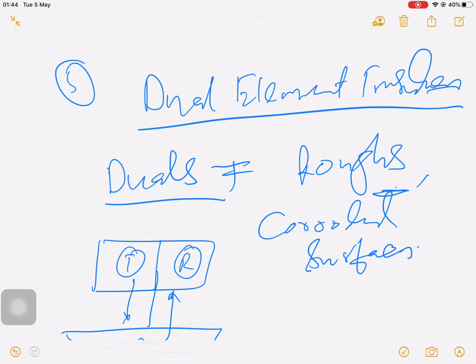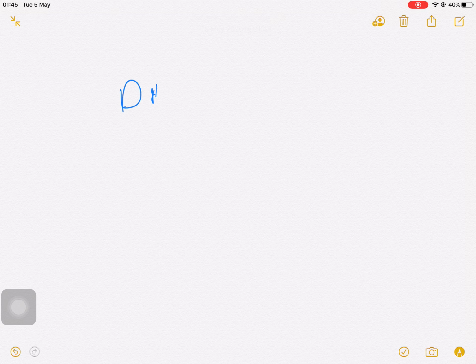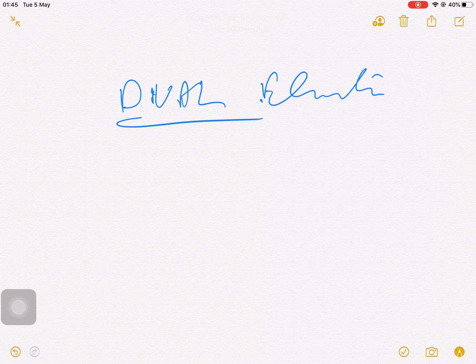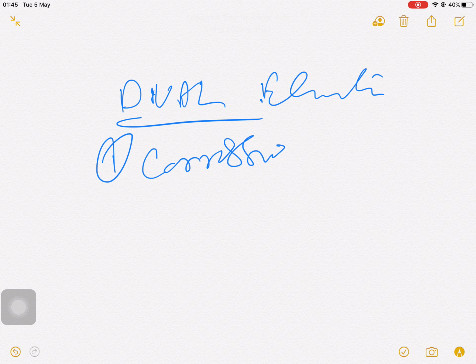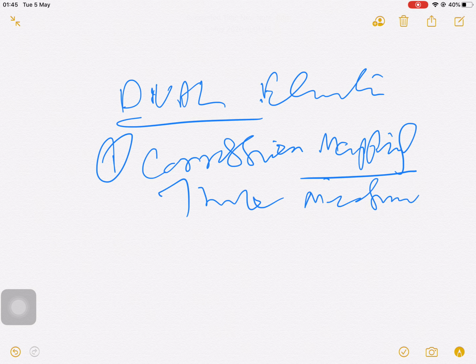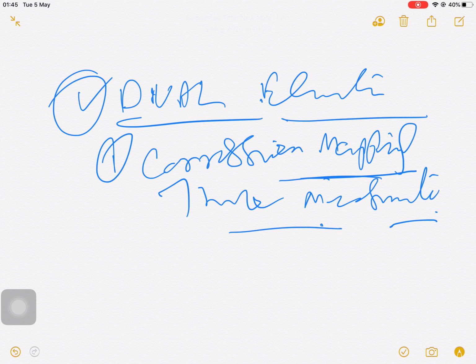select distance beneath the surface of a test piece. Although the thickness measurement with the dual is sometimes not as accurate as with other types of transducer, they usually provide significantly better performance in corrosion survey applications. So generally dual element probes are used for corrosion mapping or thickness measurement, due to the high sensitivity to pitting and improved near surface resolution. Why do we use dual element transducers in corrosion mapping? Because of the higher sensitivity to pitting.